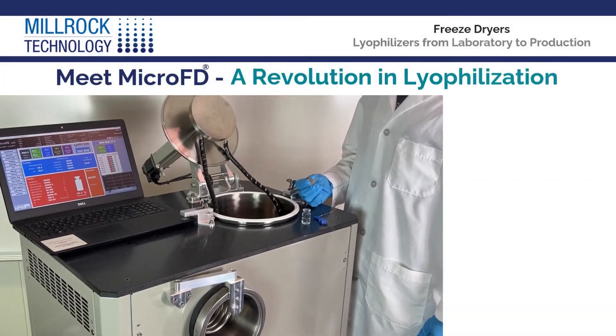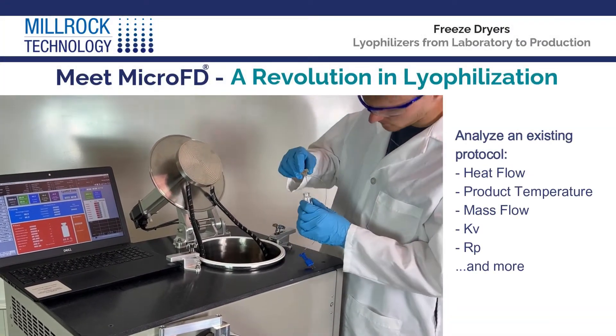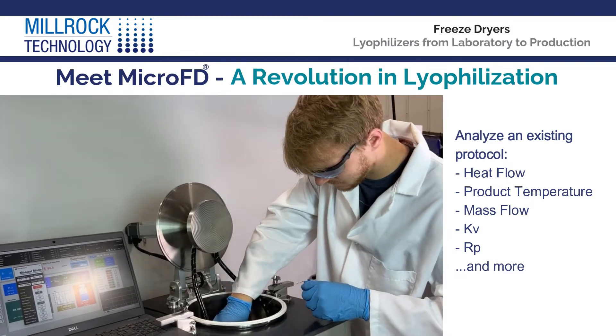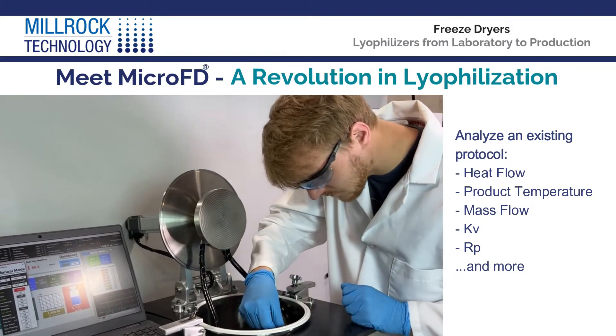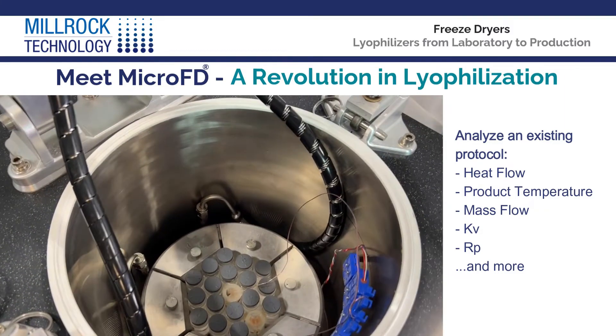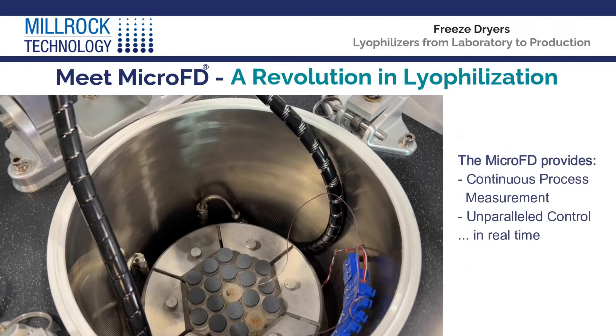Analyze your existing protocol by collecting the critical process parameter data for both the freezing and primary drying cycles, including heat flow, product temperature, mass flow, Kv, Rp, and more, determined by the most advanced process analytical technologies.